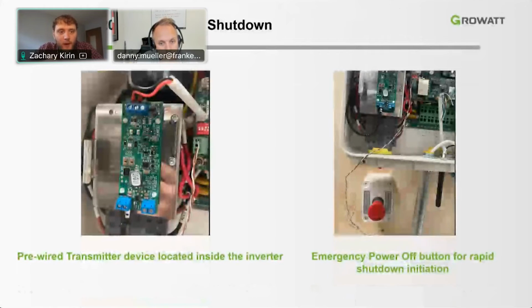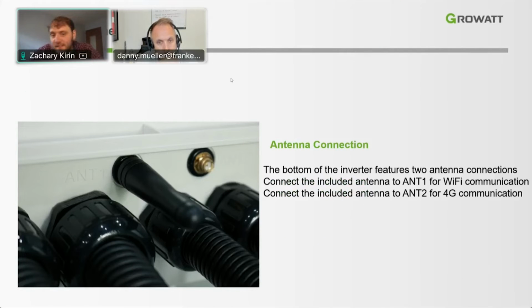For the wiring of the rapid shutdown system, again, this transmitter is what is built inside the inverter. This will be either the AP Smart or the Tigo transmitter. And then this will be an example of the emergency power off button or the rapid shutdown initiator. So this will be wired directly to that 3-pin conductor we talked about at the top here. What's important to note, there is no polarity to this. It's just a button which is asking for a signal. And then when the button is pressed, it completes that circuit and the inverter knows to instinctively turn off. So 2 different ways for rapid shutdown, either the DC disconnect or the rapid shutdown initiator button.